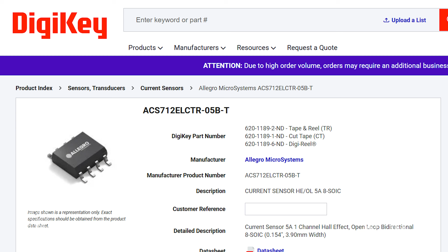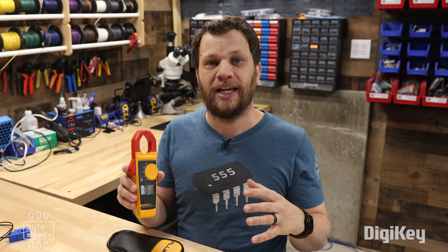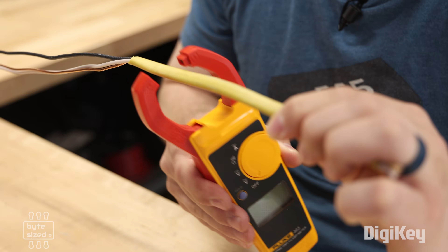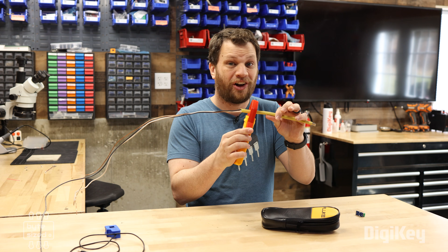The next option is a clamp meter like this, the Fluke 323, which can measure current flowing through a circuit without breaking it. Anytime current flows through a conductor, it creates a magnetic field. If you bring another conductor within that field, it induces a current in that secondary conductor. For example, if I want to measure the current flowing through this set of wires and close the clamp around the whole set, I'll actually get a reading of 0 amps, because the alternating current in the hot and neutral wires cancels out.